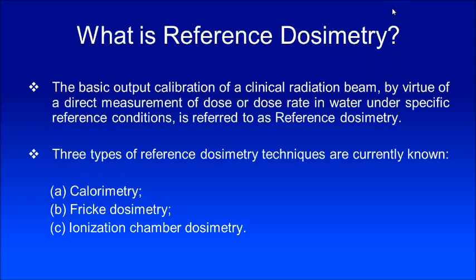What is reference dosimetry? The basic output calibration of a clinical radiation beam by virtue of direct measurement of dose or dose rate in water under specific reference conditions — this is referred to as reference dosimetry. As of today, there are three different dosimetry techniques that are considered to be reference dosimetry.